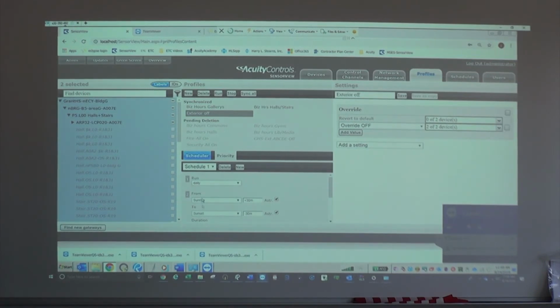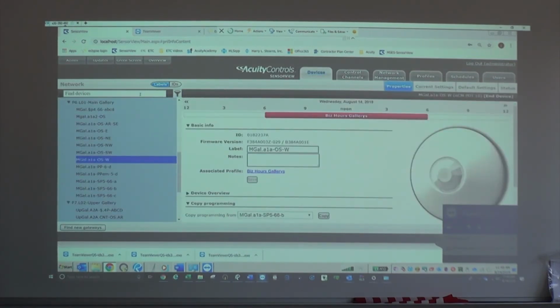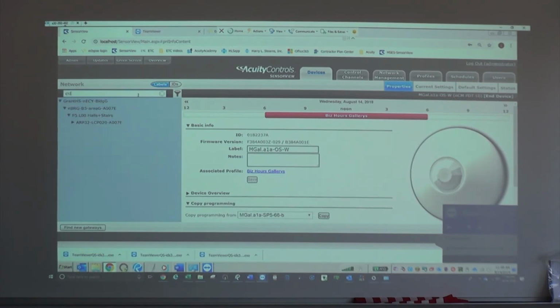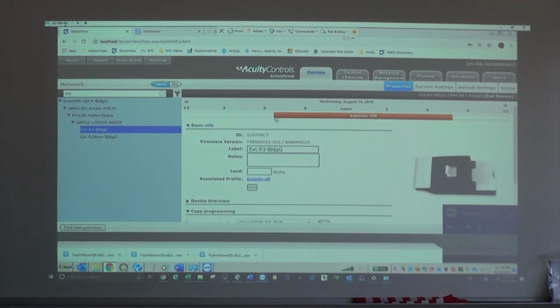But between this time, let's go back to devices and type EXT for exterior. My exterior devices on this building run from 6:39 a.m. to 7:49, because it's astronomical, it's following the sun today. That light is going to be off. Notice in the timeline up here, there isn't anything that says the light will be on, only something that says it will be off. The normal state, because we want the default setting of exterior lights to always be on, since we want a nuisance call and not an emergency call.